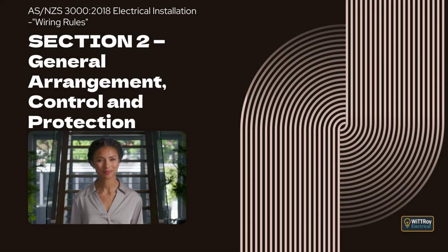Clause 2.6.2 Selection and arrangement of devices. Clause 2.6.2.1 General. Any RCD used for additional protection must be able to interrupt a circuit when earth leakage rises above its designed trip level. The load rating of the RCD must be at least the same as the maximum demand of the part of the installation it protects, or the highest rating of any overload device on that same part of the installation. Earth or bonding conductors must never pass through the magnetic core of the RCD, because this would affect the correct operation. Circuits must be arranged so the normal leakage from connected equipment will not cause nuisance tripping. We aim to keep normal leakage well below the RCD's rating.